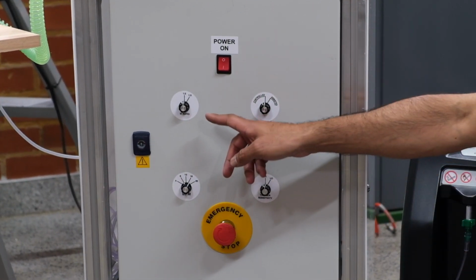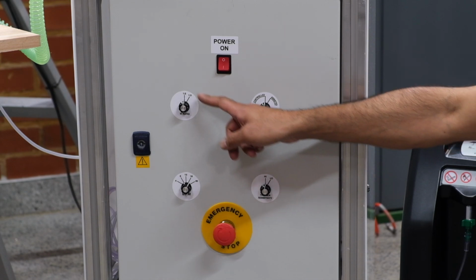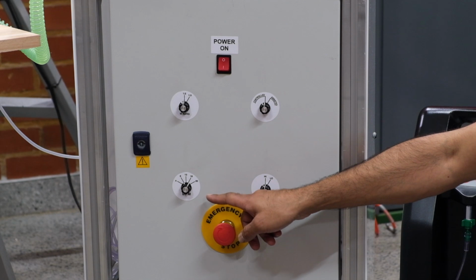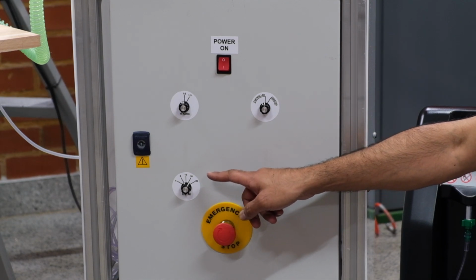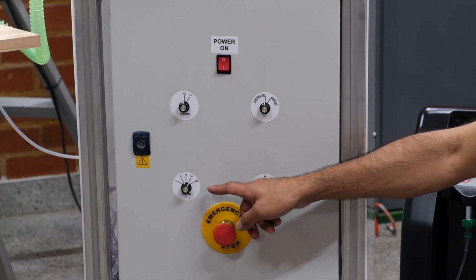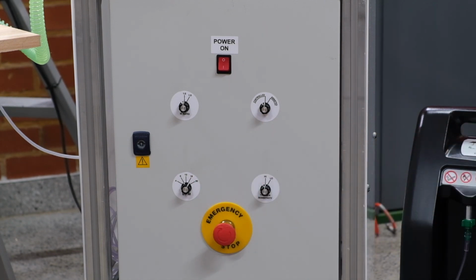The inspiratory-expiratory ratio is now set to either 1:2 or 1:3. On the breaths per minute, I've added 2 further options, so that's now 4, 8, 12, 16 and 20. That's so that the patient can take unassisted breaths in between assisted breaths.